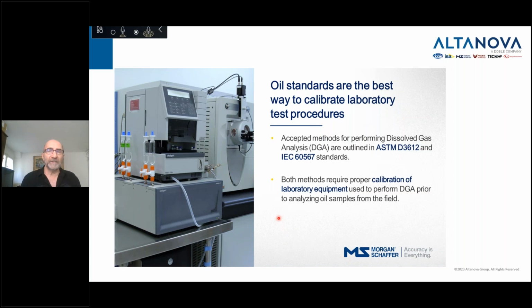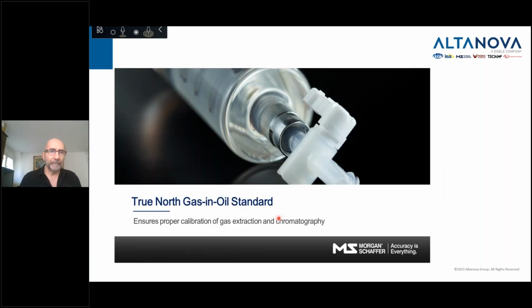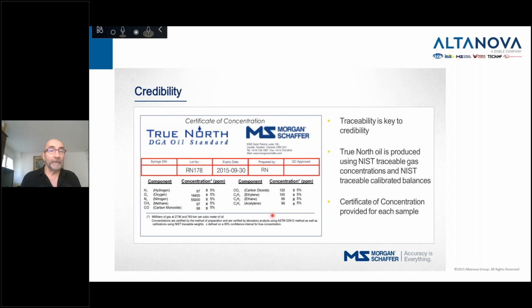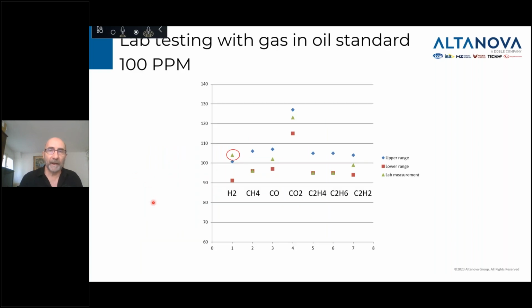So a gas in oil standard tells you not just that the GC is calibrated, but also that the extraction system is efficient. Usually what you do is send a gas in oil standard like this one, where you have the specific concentration of gases dissolved in that oil with an accuracy of plus or minus 5% in general. And the lab will mostly inject it. And here's an example of a lab we've worked with, where we sent a 100 ppm gas in oil standard.